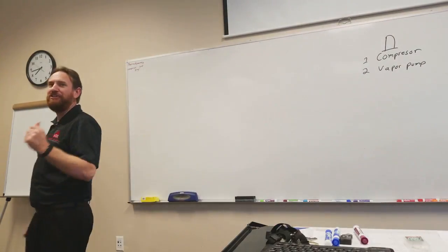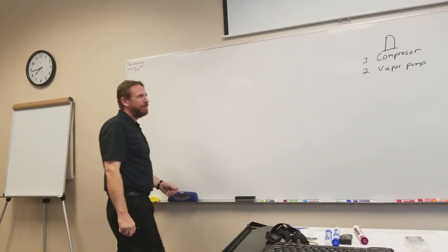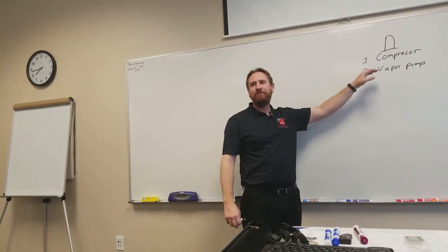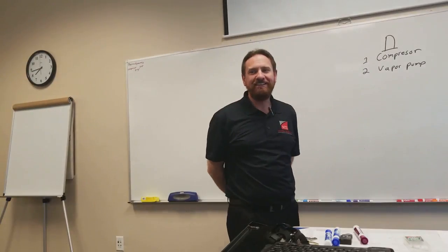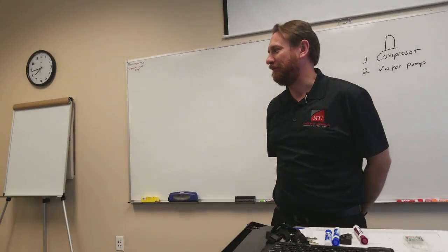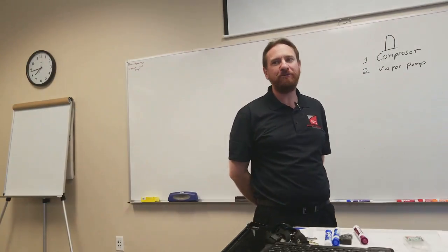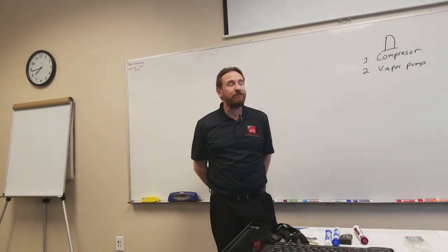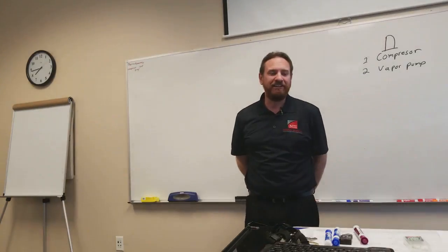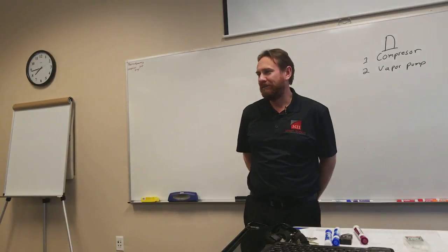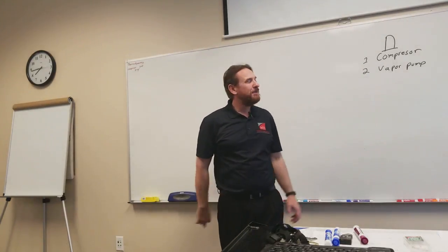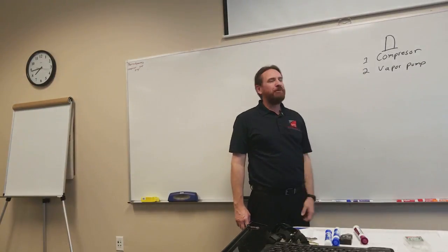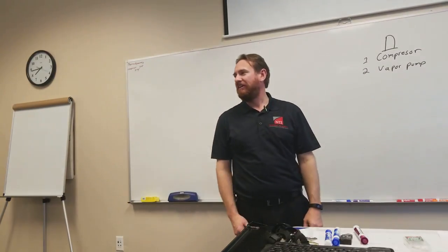No. Because it's a vapor pump, it can only pump vapor, it can only pump gases. It cannot pump a liquid, and the reason is you cannot compress a liquid. You can sling a liquid, you can push a liquid. Liquid pumps are really not pumps, they're actually centrifugal. A centrifugal pump is actually slinging the liquid. But in a vapor compression system, you cannot compress a liquid.